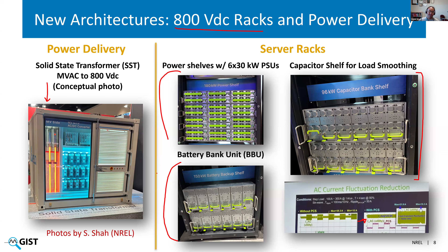Switching gears a little, let's look at how the AC UPS operation mode impacts the modeling. There are three different operation modes. One is the double conversion mode, where power flows directly through a back-to-back AC-DC-AC converter. In this case, the grid will see the AC UPS first. It will not see the PSUs and IT racks. So it makes our job as power system engineers a bit simpler, because we can look at these multi-megawatt converters, which look very similar to inverters in battery or PV power plants at the front end.